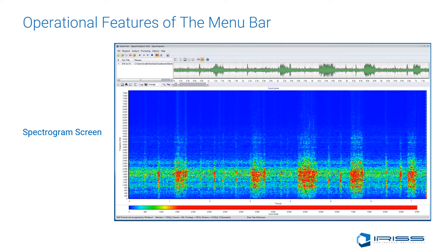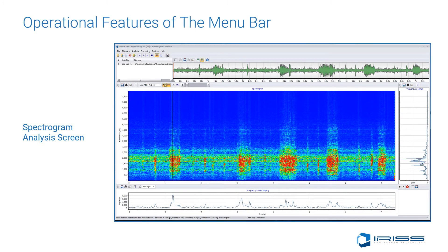Spectrograms give the analyst the ability to analyze the signal with three parameters simultaneously: time, amplitude, and frequency. Time is on the x-axis, frequency is on the y-axis, and amplitude is defined with color. To display the spectrogram, select the spectrogram view, which opens a blank screen, then go back to the Analysis tab and click Compute. The spectrogram analysis screen combines the frequency spectrum, time signal, and spectrogram screen for use in determining harmonic indications.